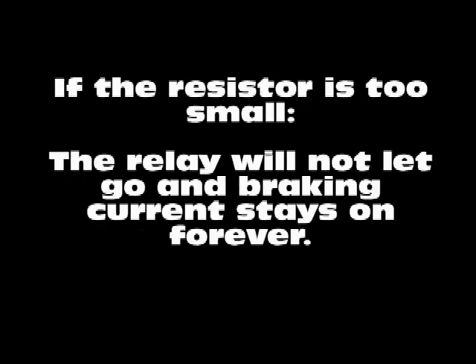If the resistor is too small, the capacitor will never build up enough charge, and the current through the coil will never stop. The only purpose of the resistor is to discharge the capacitor while the motor is running, so the capacitor will be empty for the next braking cycle.